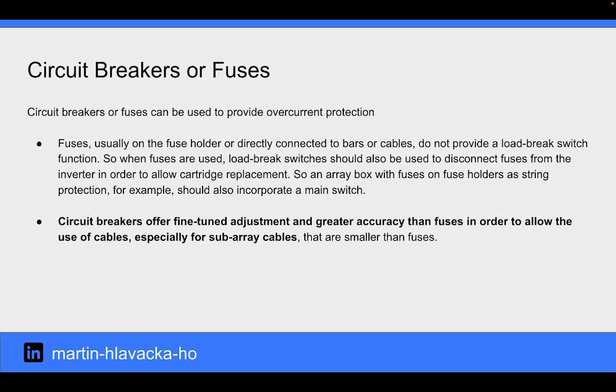Fuses, usually on the fuse holder or directly connected to bars or cables, do not provide a load break switch function. So when fuses are used, load break switches should also be used to disconnect fuses from the inverter in order to allow cartridge replacement. So an array box with fuses on fuse holders as string protection, for example, should also incorporate a main switch. Circuit breakers offer fine-tuned adjustment and greater accuracy than fuses in order to allow the use of cables, especially for sub-array cables that are smaller than fuses.